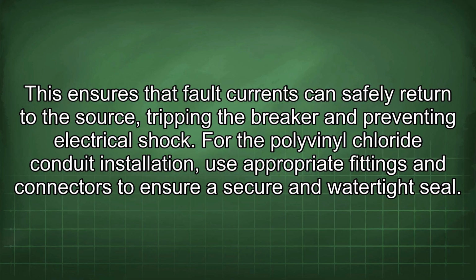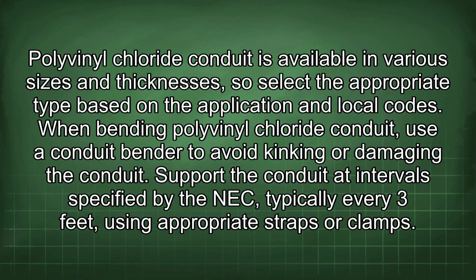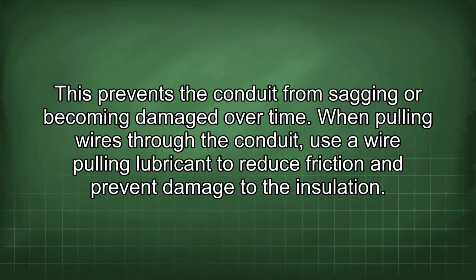For the polyvinyl chloride conduit installation, use appropriate fittings and connectors to ensure a secure and watertight seal. Polyvinyl chloride conduit is available in various sizes and thicknesses, so select the appropriate type based on the application and local codes. When bending polyvinyl chloride conduit, use a conduit bender to avoid kinking or damaging the conduit. Support the conduit at intervals specified by the NEC, typically every 3 feet, using appropriate straps or clamps. This prevents the conduit from sagging or becoming damaged over time.